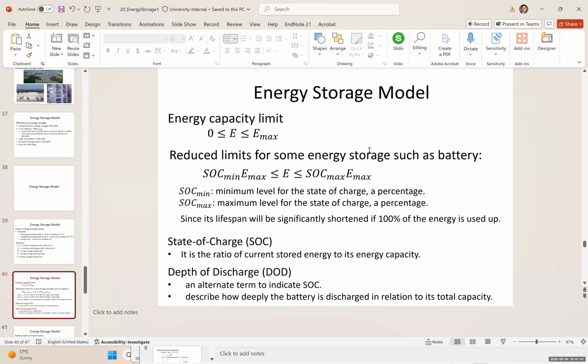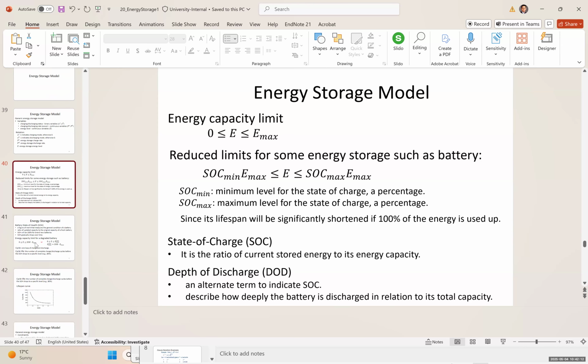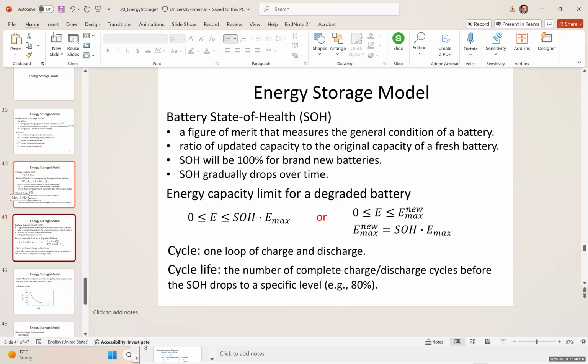The SOC is the state of charge, which is the ratio of current stored energy to its energy capacity. And we have the DOD, which is the depth of discharge, an alternate term to indicate SOC; it describes how deeply the battery is discharged in relation to its total capacity. So if the battery is charged and discharged between 20 and 80%, it's going to last, for example, 5 or 10 years. But if it's charged from 0 to 100% and back to 0, it's just going to last a couple of years. So we have these BMS, battery management systems, that are able, for example, to stop charging when the charge reaches 80% to protect and extend the life of the battery.